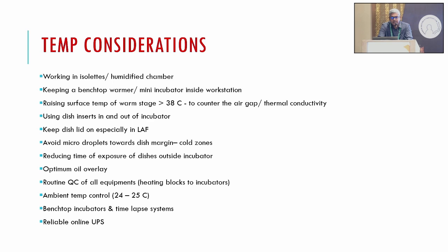Which is not very expensive also. Raising the surface temperature of warm stages to more than 38 degrees can help to counter this air gap and thermal conductivity. When you're handling dishes in and out of the incubator, you can use the dish inserts to maintain the temperature. Keep the dish on, lid on, especially in LAF. And when you're culturing with micro droplets, avoid the micro droplets towards the dish margins.